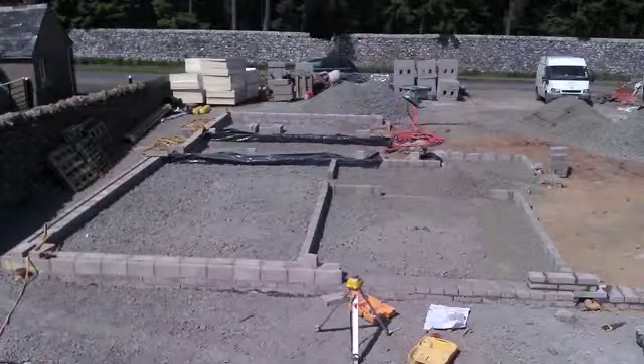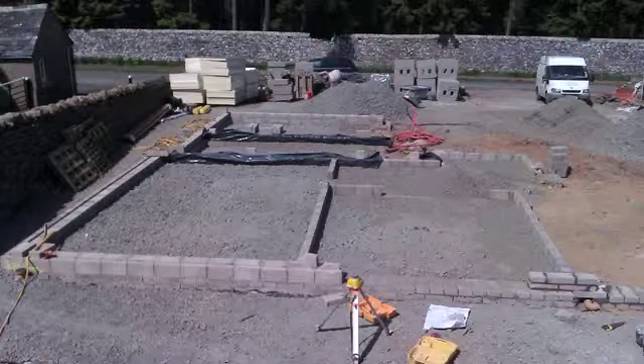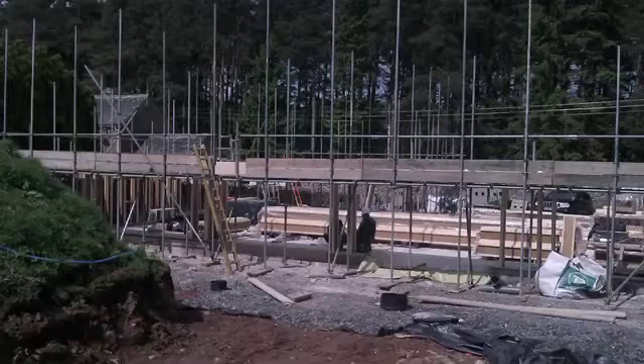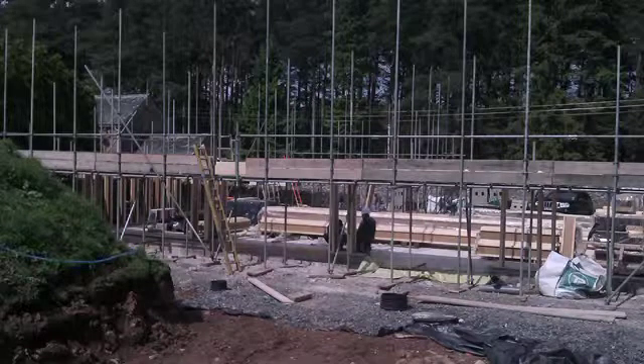The downside of a highly insulated box is the thermal mass of it. So all our ground floor is a concrete slab with the underfloor heating built into it, just constantly trying to put thermal mass back into the building really. We've got a ground source heat pump to do the heating and hot water, and then photovoltaics on the roof. Originally we were looking at putting solar thermal in. I've done away with that because by the time we've got a ground source heat pump, which is obviously efficient, combined with the PV, it outweighed the benefits of going to solar thermal as well.